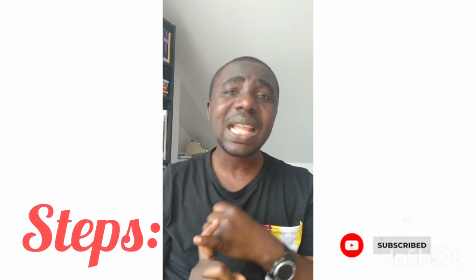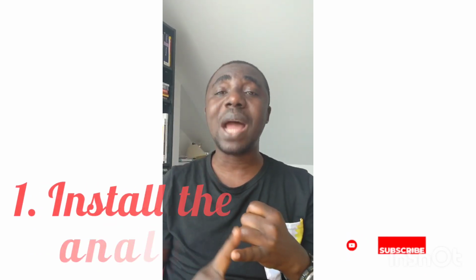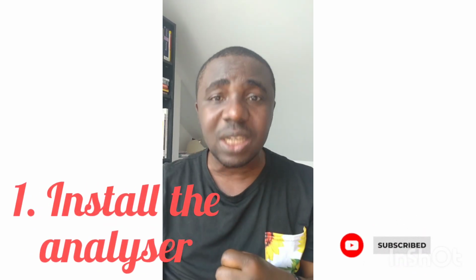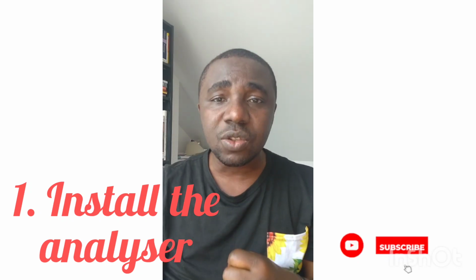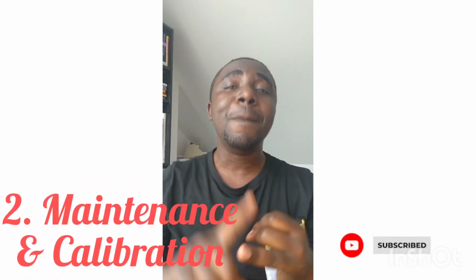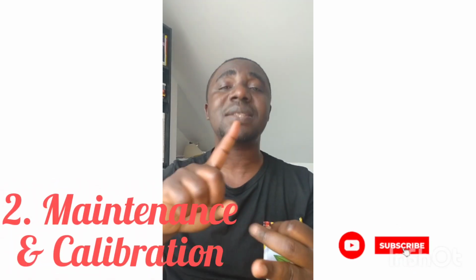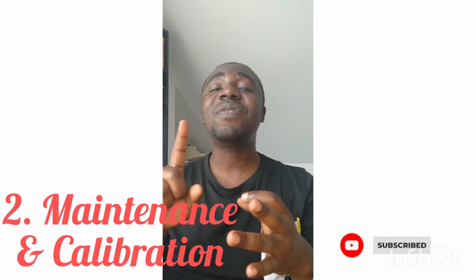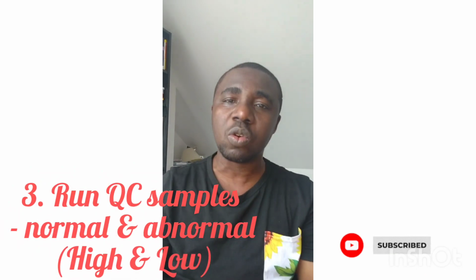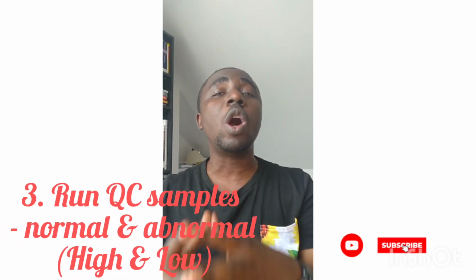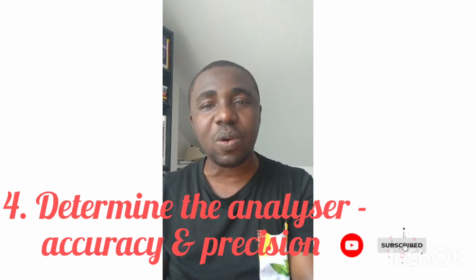So if I'm going to put it in steps: step one in analyzer validation is, of course, you install the analyzer. Step two, after it is installed, is to do analyzer maintenance and calibration. After maintenance and calibration, the next step is to do the quality control, checking how precise and accurate it is.